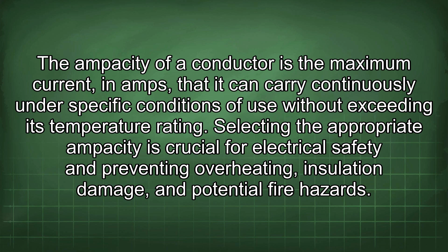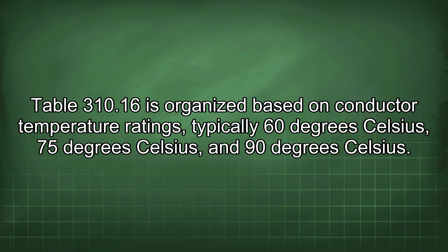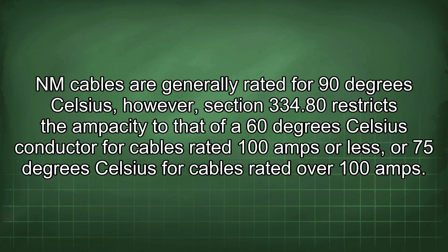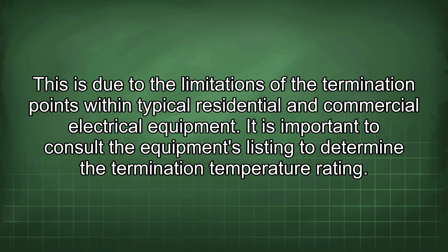Table 310.16 is organized based on conductor temperature ratings, typically 60 degrees Celsius, 75 degrees Celsius, and 90 degrees Celsius. NM cables are generally rated for 90 degrees Celsius, however, Section 334.80 restricts the ampacity to that of a 60 degrees Celsius conductor for cables rated 100 amps or less, or 75 degrees Celsius for cables rated over 100 amps. This is due to the limitations of the termination points within typical residential and commercial electrical equipment. It is important to consult the equipment's listing to determine the termination temperature rating.